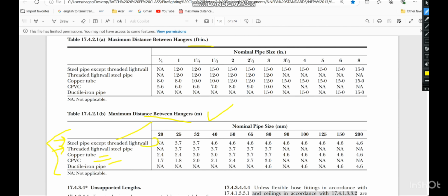Let's say that we have one 80 mm pipe. For the 80 mm pipe, 4.6 meters they have given. That means from one support to another support, the distance must not exceed 4.6 meters for the steel pipe. So this rule we have to comply with while providing the supports.